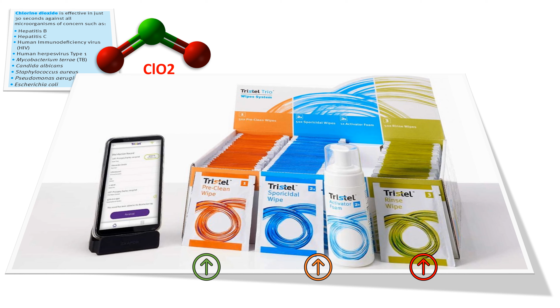In our gyne unit, we are using the Tristel Trio Wipes system for ultrasound decontamination. The Tristel Trio Wipes system comes with three wipes. Wipe number 1, more or less orange in color, is for pre-cleaning of the probe. Wipe number 2, the Tristel wipe, will be mixed with the activator foam, and it is used as the active decontamination ingredient. And the third wipe, more or less green in color, called the rinse wipe, is for cleaning after the decontamination process.